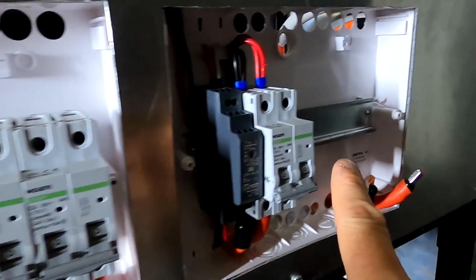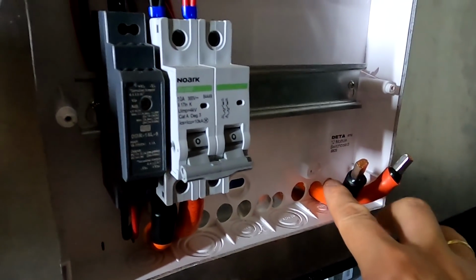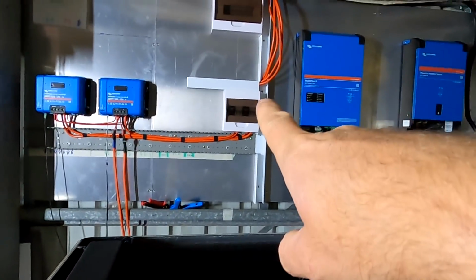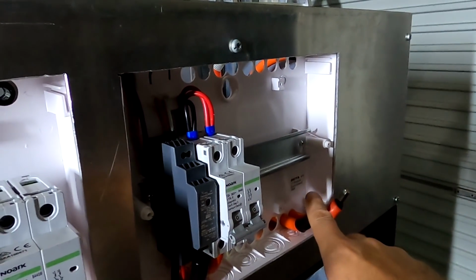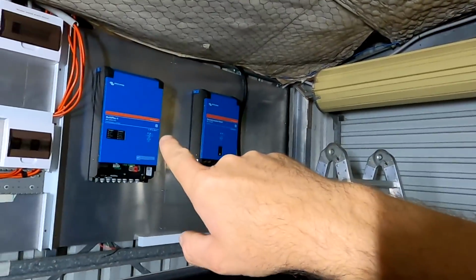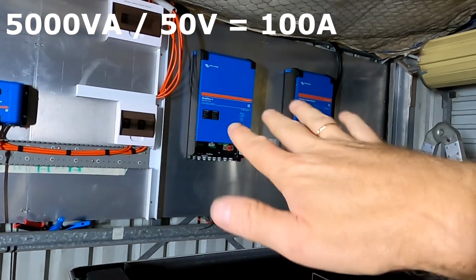But anyway, this is only one problem I have, which is in the future until we upgrade the solar here. The other problem is actually further here. I have already stolen this 63 amp circuit breaker here for our solar isolator box there. It's in there. And I thought, well, I need to order some new ones for our inverters, right? Unfortunately not. Because this all worked with the old inverter because it was only a 3 kVA inverter, but the new one is a 5 kVA inverter. And obviously 63 amps is not enough to power a 5 kVA inverter, because 5000 divided by 50 volts of our battery is 100 amps. So we need to have at least 125, maybe 150 amp.